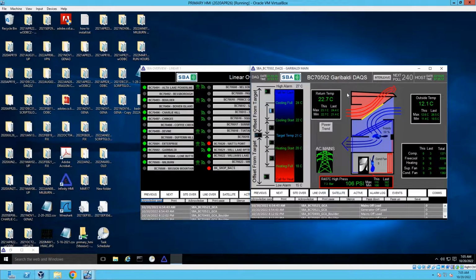On normal operation, the supply fan is on 24 hours a day to keep air circulating. When the temperature rises above the target temperature, the unit will free air cool, which means push hot air from in the building to the outside, and bring cooler air from outside into the building. This eliminates the compressor used during DX cooling in normal air conditioners, which offers a substantial reduction in power consumption.